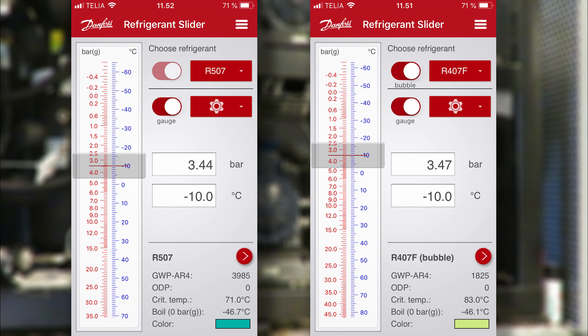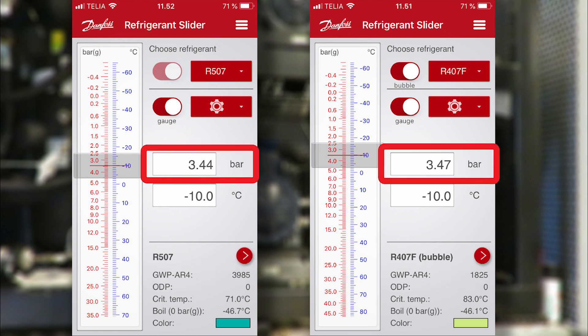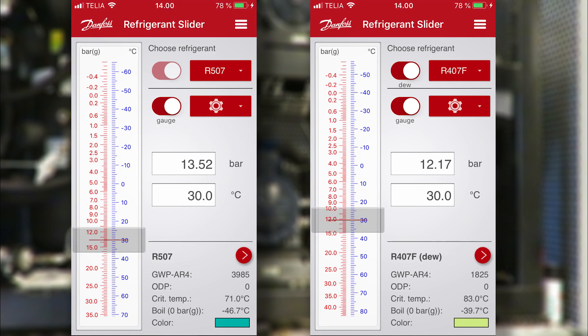We've pulled up the two refrigerants on the same screen, so we can compare the numbers directly. Let's have a look at the GWP — as you can see, there's a significant difference in the values, where the older refrigerant is more than double the new. If we look at the evaporation pressure, they are almost the same, with just an insignificant difference. If we look at the condensing pressure, the difference is larger, but still to the good side, so to speak. The R407F has a lower pressure at 30 degrees Celsius, so no need to do anything radical to the system.